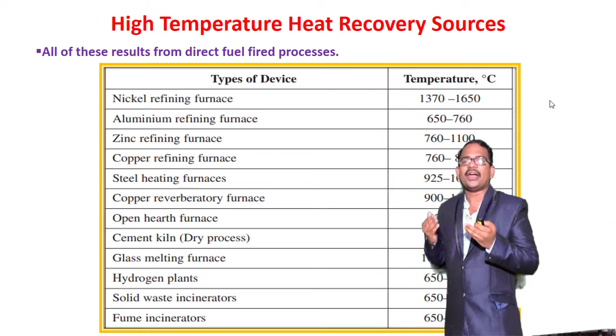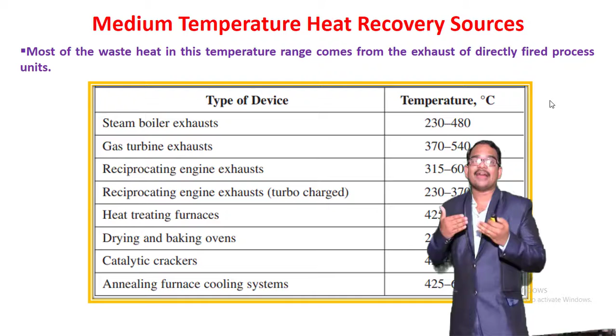And the next one is medium temperature heat recovery sources. What are the examples of these? Steam boiler exhaust, at a temperature of 230 to 480 degrees centigrade. And the next example, gas turbine exhaust, with a temperature of about 370 to 540 degrees centigrade. All these are examples of medium temperature heat recovery sources. Most of them are obtained from the exhaust streams of directly fired processes.